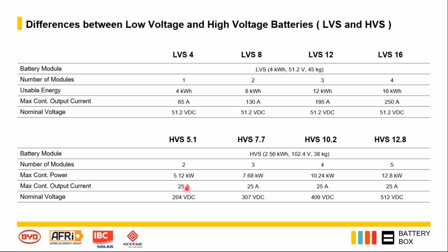So it's just something to remember, that the current that you can get out of one tower will always remain the same at 25 amps. If you have 2 towers in parallel, then it'll be 50 amps that you can get out of your battery bank. And if you have 3 towers in parallel, it'll be 75 amps. But for each tower, you'll always only get 25 amps maximum out of the tower.